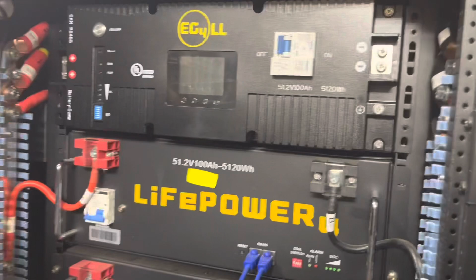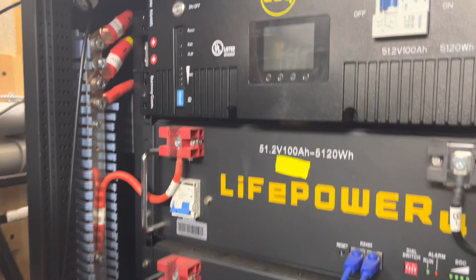Actually, it's grounded back up in there. You can't see it because the original racks did not have a provision for a ground. So we made one, and then I ohmed it to the frame, to the battery, after we clamped it up to the slots with these screws. Even though a lot of them didn't line up, we did manage to get at least 2 screws in every battery. So I didn't need them to physically restrain them so much as I wanted them for the ground.